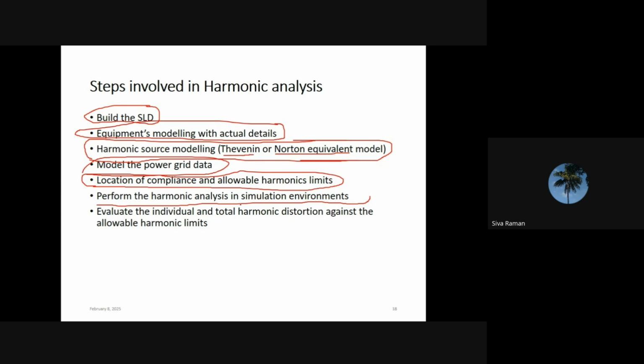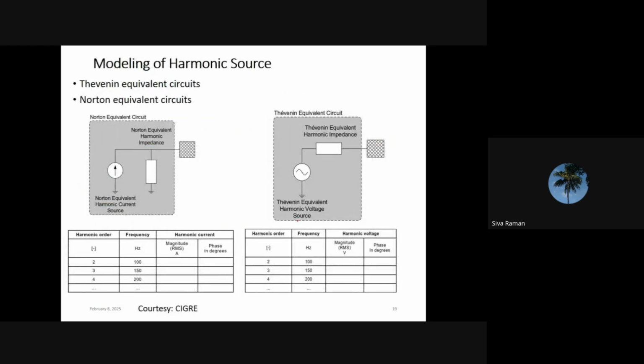Then after performing the harmonic analysis, we have to evaluate the individual as well as the total harmonic distortion against the allowable limit. So these are the typical steps involved. About the modeling of the harmonic source, as I explained, we have to model it as a Thevenin equivalent or Norton equivalent. Mostly, we will model the harmonic source as a Norton equivalent.